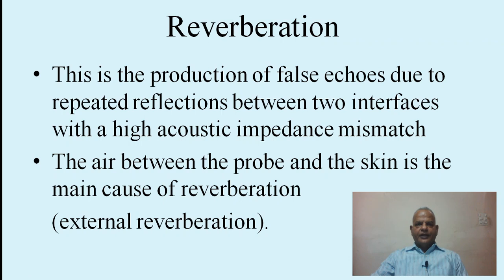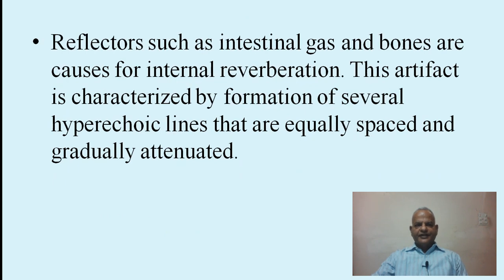The most common artifact is reverberation. Reverberation is the production of false echoes due to repeated reflections between two interfaces with a high acoustic impedance mismatch. The air between the probe and the skin is the main cause of external reverberation, so a gel must be applied to provide a medium for sound to travel. Reflectors such as intestinal gas and bones cause internal reverberation. This artifact is characterized by several hyperechoic lines that are equally spaced and gradually attenuated.